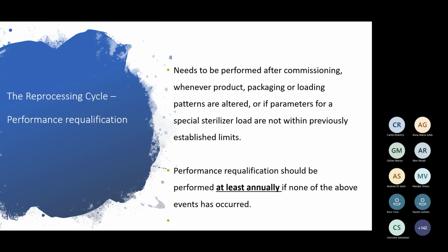Or if parameters for a load, special sterilizer load, are not within previously established limits. So sometimes we'll get people going, oh, well, we're using a plastic item, so we want to sterilize at 121 degrees. Do I need validation performed? My answer is yes, because they're two totally different load types at two different temperatures. So if you're processing some metal instruments at 134 degrees, you need validation for that load. If you're processing some plastics or smaller items that can't be processed at the higher temperature, then you need another validation to prove the lethality of the processing at the 121 degrees. So yes, you do need different validations.